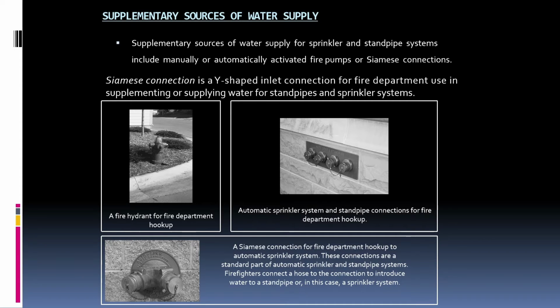First one is supplementary sources of water supply. Supplementary sources of water supply for sprinkler and standpipe systems include manually or automatically activated fire pumps or Siamese connections. A Siamese connection is a Y-shaped inlet connection for the fire department used in supplementing or supplying water for standpipes and sprinkler systems. And these are the photos for the supplementary sources of water supply.